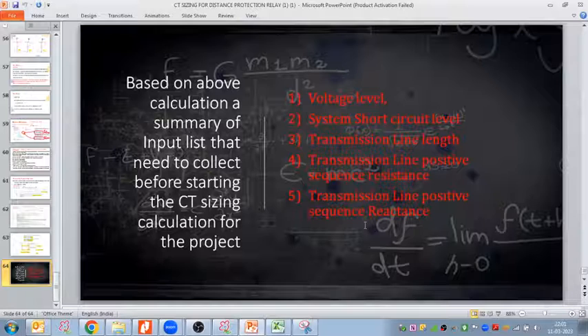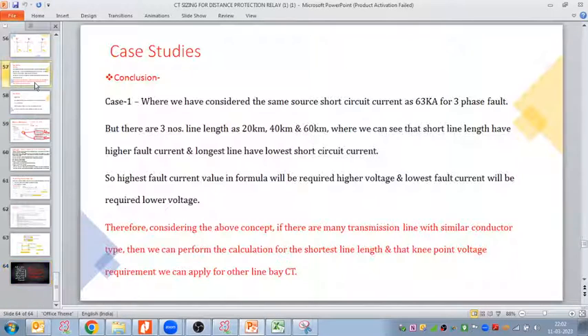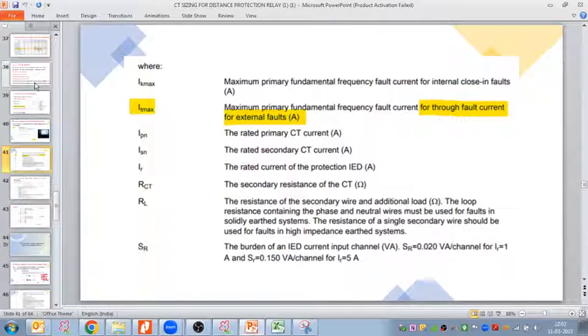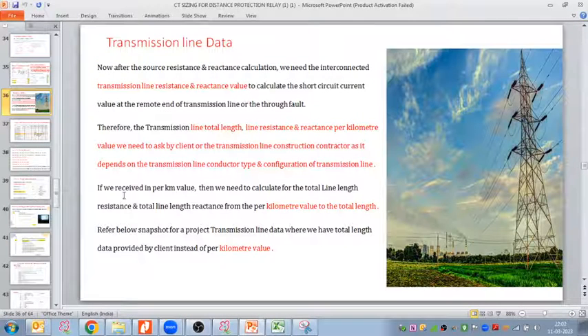And why not the zero sequence? The zero sequence comes in when a single phase to ground fault happens, and in that case you require the zero sequence impedance calculations. We will discuss that also in the calculations. You can ask for the zero sequence impedance, but if you are not getting it, there is no need to wait, you can start the calculations. Coming back to the transmission line, if we receive the per kilometer value for the resistance and reactance, then we need to calculate the total length resistance and total length reactance. Whatever value you get, cross check whether it is the total length value or the per kilometer value. If the client says it is per kilometer, then multiply it by the total length to get the value for the total length.